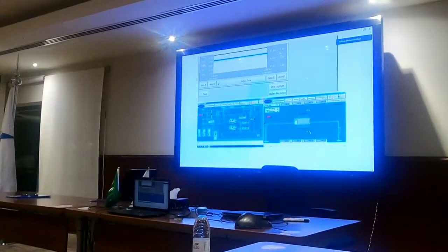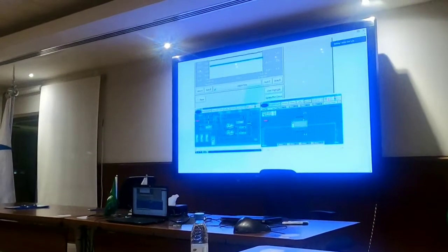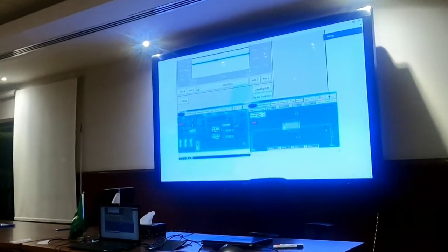I can't get a closer look, he put them side by side for some reason, he thought this was the best place. We need to have a clear reading for those. He's put them on a Word document, but I can blow these screens up for you so you can see these numbers better before I send you that data. But this represents your chiller right here. These, of course, are the air temperature trees that we've seen earlier on the video and the still pictures that I took for you. Over here, of course, are the water flow meters and the temperatures both in and out. So that's important. This shows everything on the inside of the test chamber.